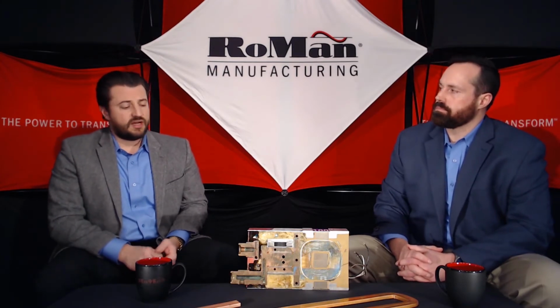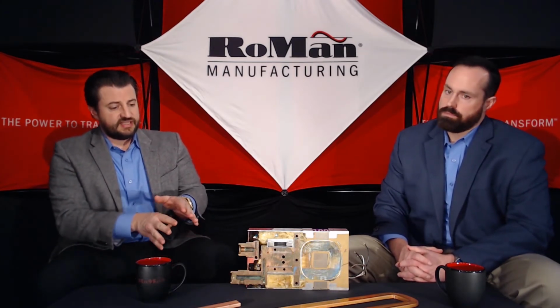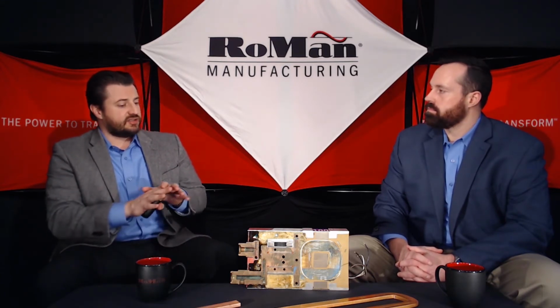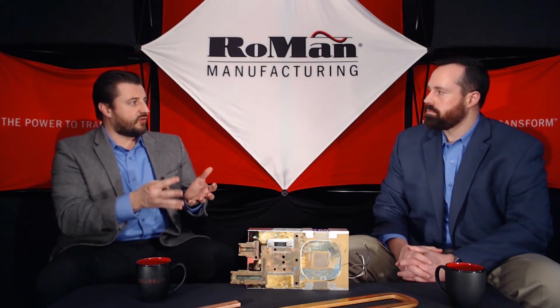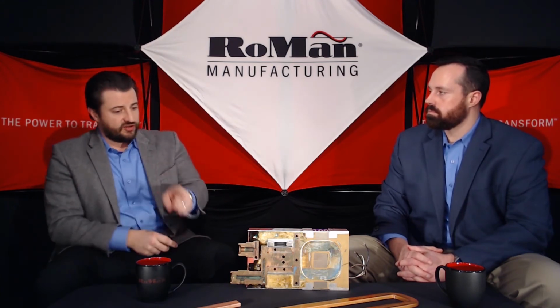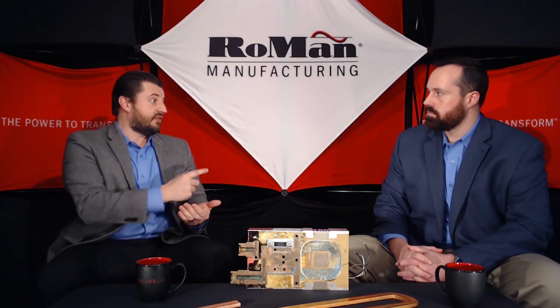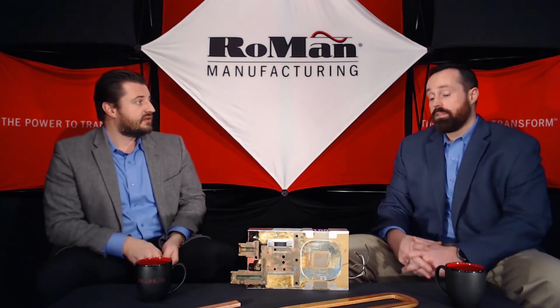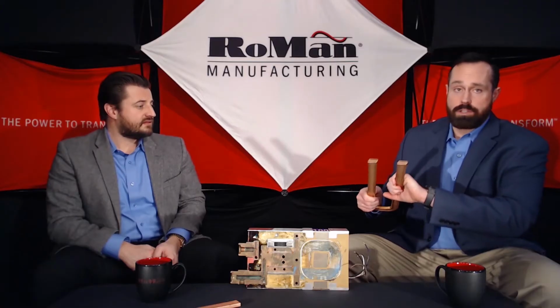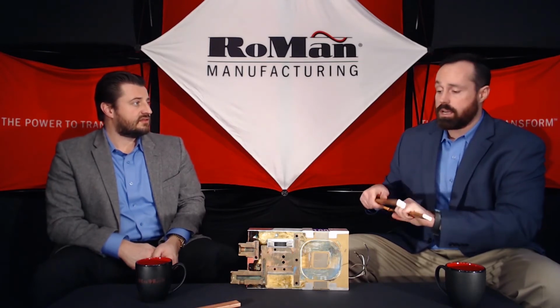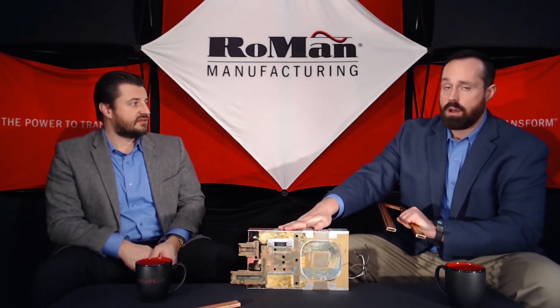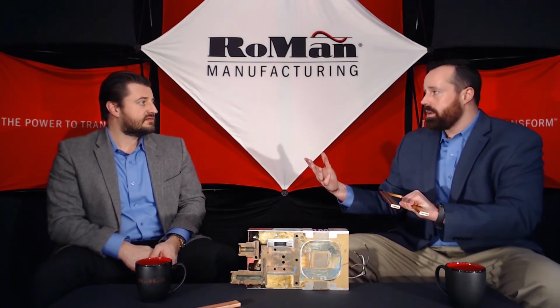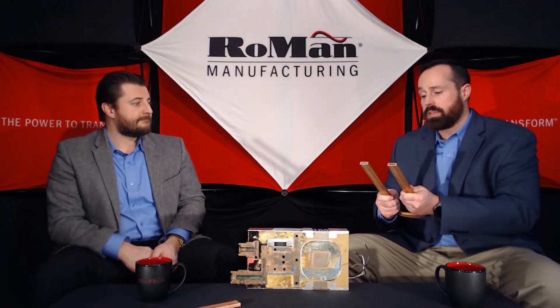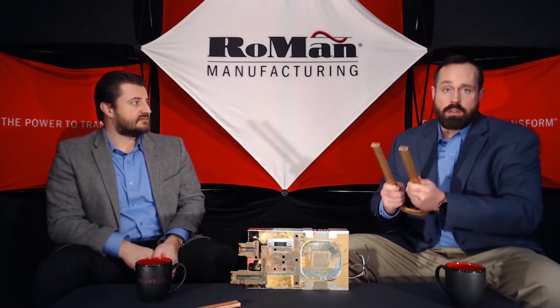Okay. So based on seeing the water-cooled copper bars, you're not actually encasing the transformer with a water jacket and then running the water through the jacket. You're pumping water directly in, almost in through the middle of the coil. That's exactly right. So when we look at channel bus bar, the water actually goes right through the conduit. It is not going through any kind of jacket or anything other within the transformer.